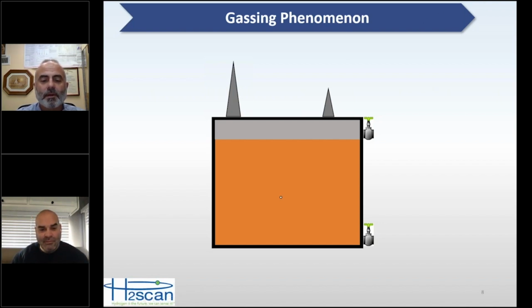Okay, so you've got some problem inside the transformer that starts generating hydrogen. Initially that hydrogen, of course, is lighter than the oil, and so it migrates up. If you've got a nitrogen blanket on your transformer, it goes up into the headspace of the transformer. And so the first place you're going to see that, and the fastest, is if you have a hydrogen monitor that's monitoring in the headspace. Eventually, once there's enough hydrogen in the headspace, the hydrogen actually starts dissolving in the oil.